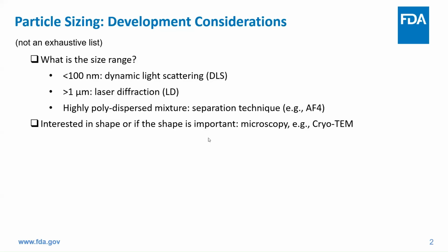And also, I think we mentioned the first day, second day, that oftentimes the shape of the particles can be important if that's something you are really interested to know, like how does it impact the laser diffraction results if it's really needle-shaped particles impacting the scattering diffraction pattern, or what are the particles? Is it oil, or is this a glass, or is it aggregate? You might want to see the shape, the morphology of the particles by performing some sort of image analysis.